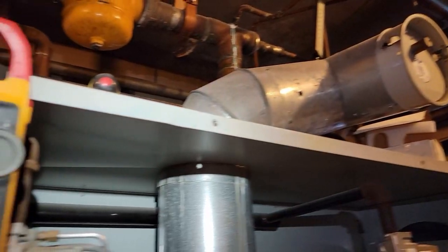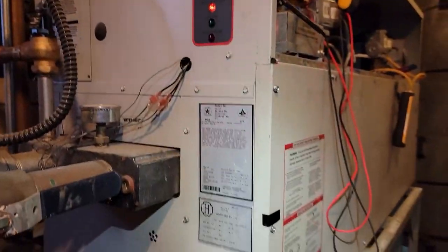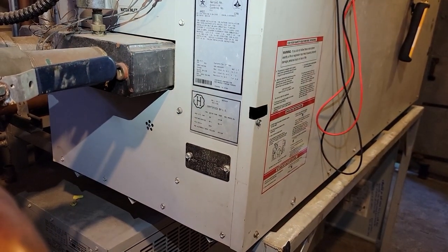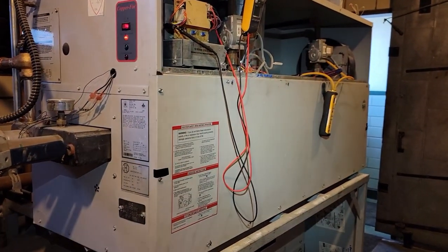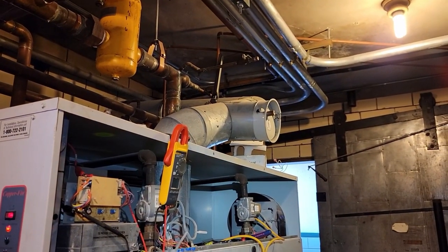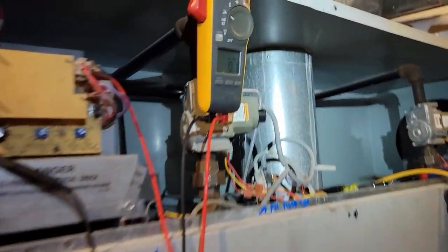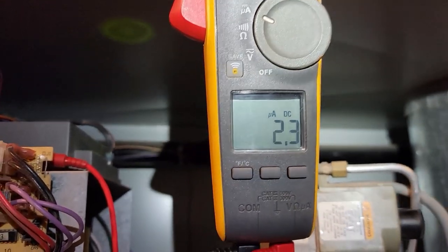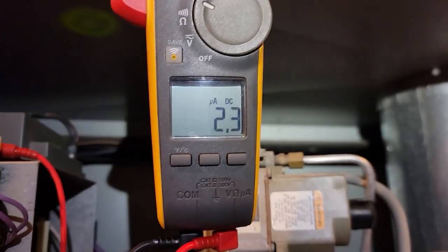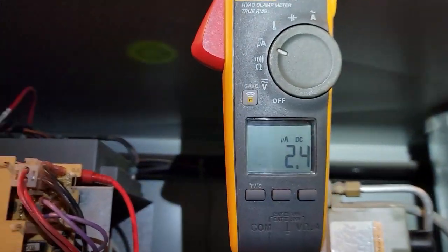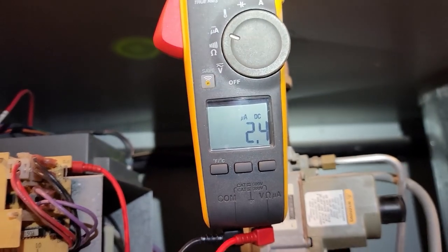Now the consequences was originally that my CO levels were high, but if the boiler isn't going to run, that's more of an issue than anything else. At that point, as much as I hate to say it, it might be time for a new boiler. We've done everything you can do. We've cleaned the heat exchanger, we've cleaned the burners. I pulled them out, washed them out, inspected everything. We checked draft up there in the flue. They want two, and we're right at 2.3, so it's a little slow on the sensor, but honestly that's pretty good.